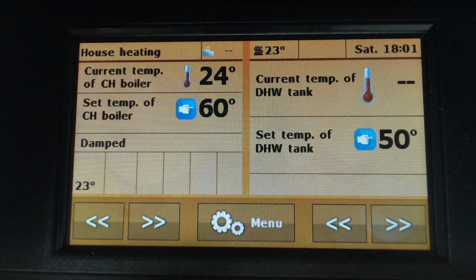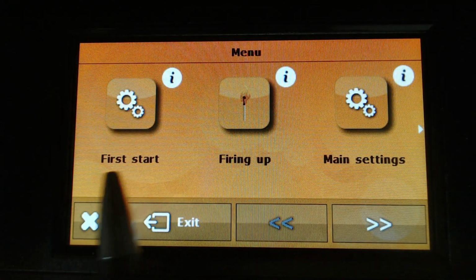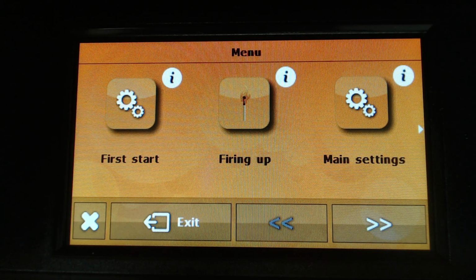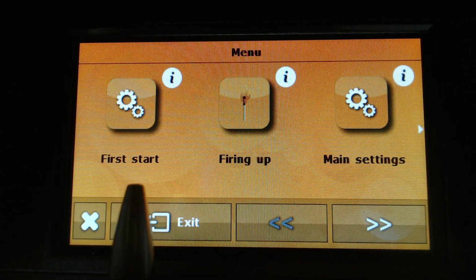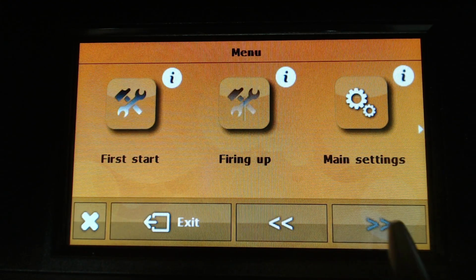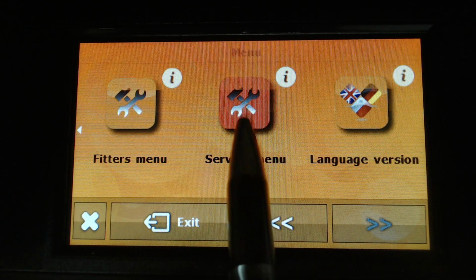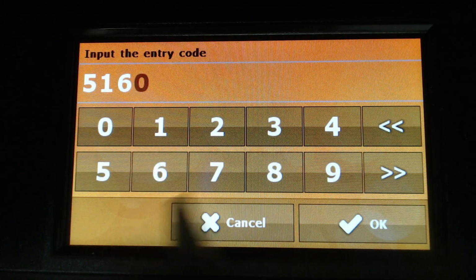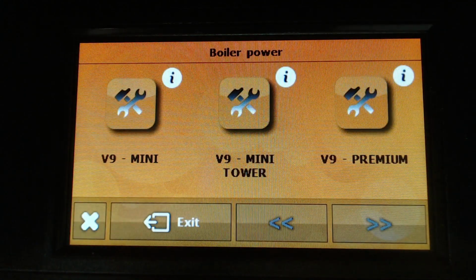So for people who already installed our boilers, in the menu there is a function called first start, where you select standard settings of the temperatures and other important parameters, and one of those is power selection. We will not go through the full first start of the boiler because it takes time, and I will show you a faster way to select the power. If you go to the service menu and enter the password, which is 5164, it will allow you to select the power of the boiler directly without needing to go through the first startup. Of course, when you start the boiler for the first time, you should go through the first startup in the standard way. This way is just simplified to show you faster how you can select the power.